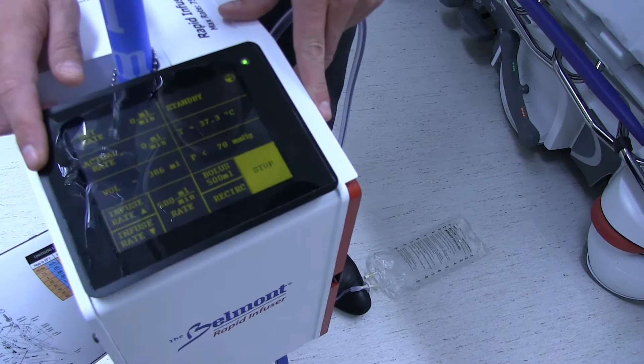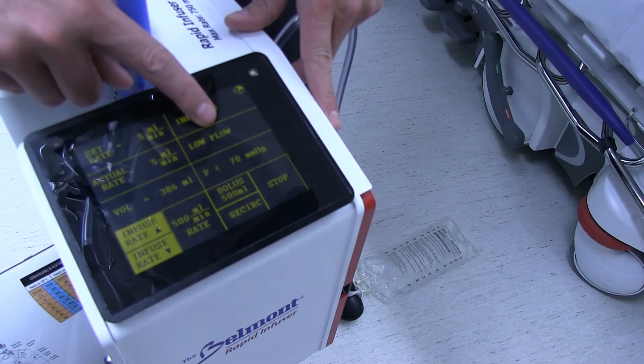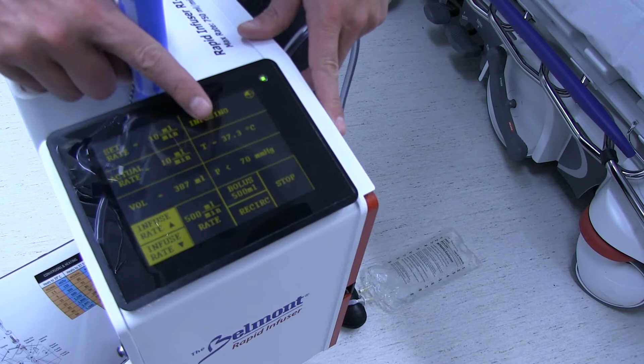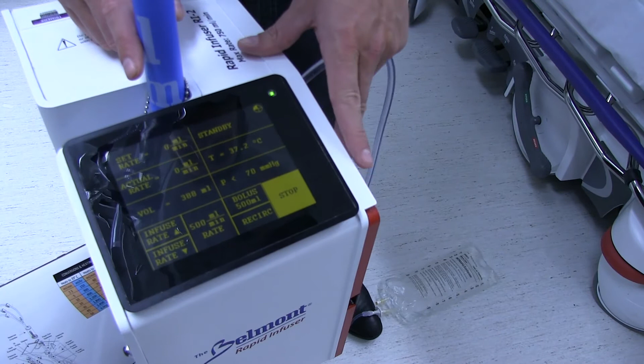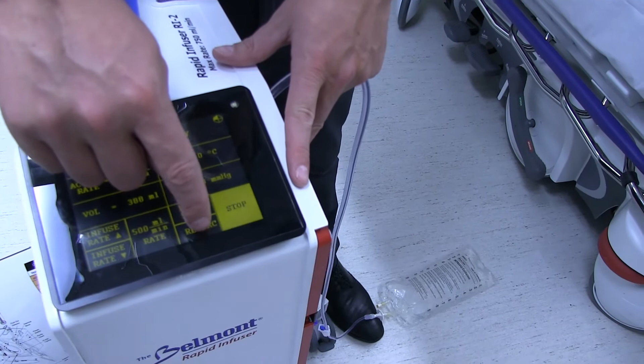The heat's always on. It stays between 37 and 39. The only time it doesn't heat is when it's at 2.5 or 5 a minute, because it's going so slow it says low flow. But after the initial prime, it starts at 10, and that's where the heat comes on. Now, the other time it doesn't heat is when it's on battery power. So, if the battery's fully charged, you've got 30 minutes of transport time. It doesn't actively heat when it's unplugged, so press this recirc button while you're still plugged in.